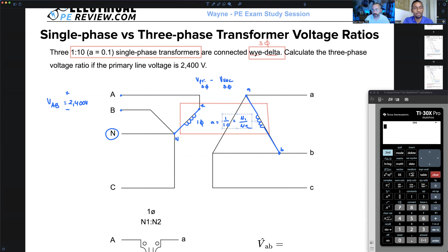So the key here is realizing that since I'm Y connected on the primary side, we don't have the full line voltage applied to the primary winding. Since it's Y connected, we've got the line to neutral voltage, or the phase voltage, applied directly on this primary winding. That's where we're going to have a sneaky square root of 3 pop up.